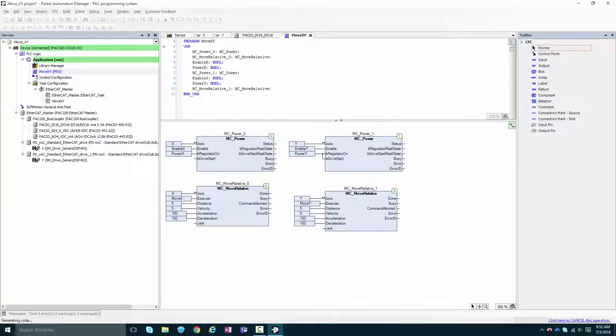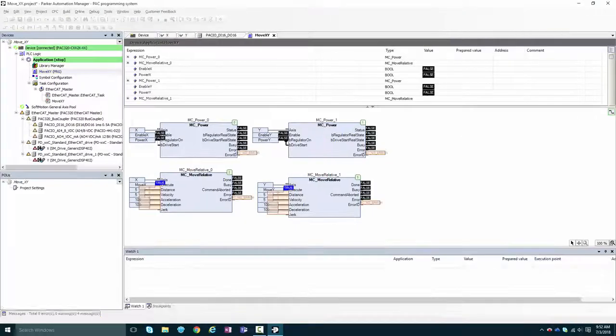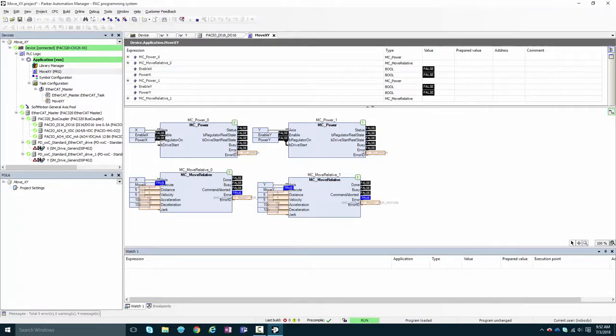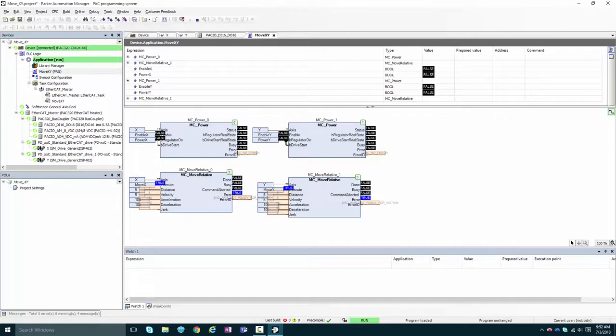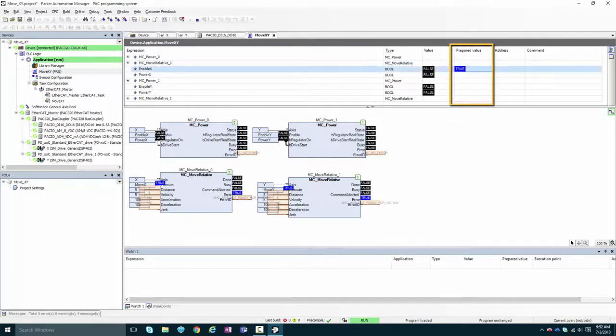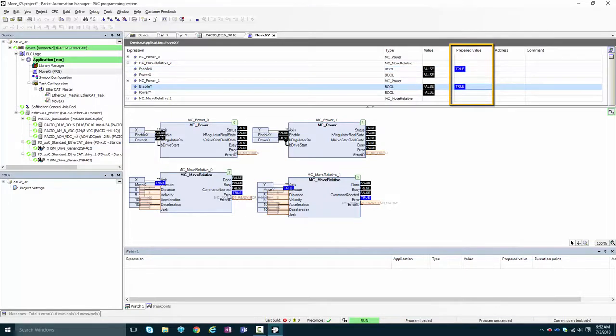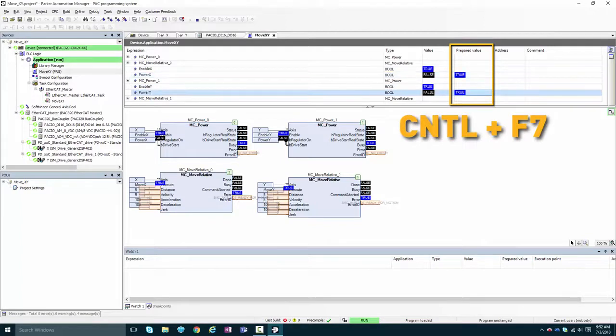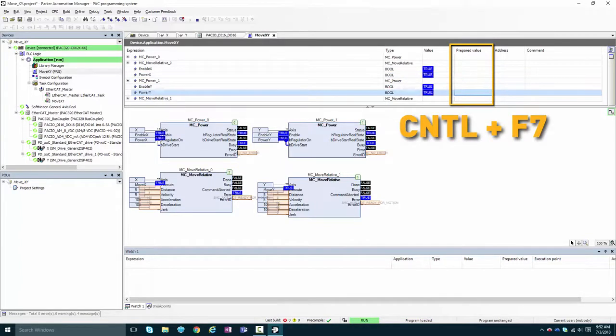And now let's download and run. There are a few variables I did not tie to physical inputs, but luckily Automation Manager allows us to force them by using the online mode of the variable declaration window. Simply click the bool to true in the prepared value column and write using control F7. Let's test our switches.